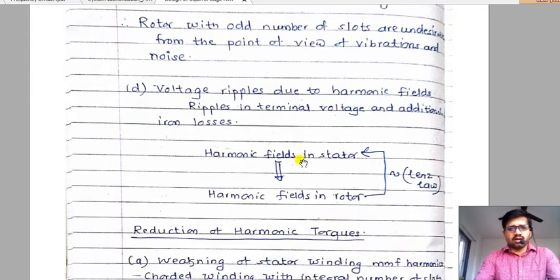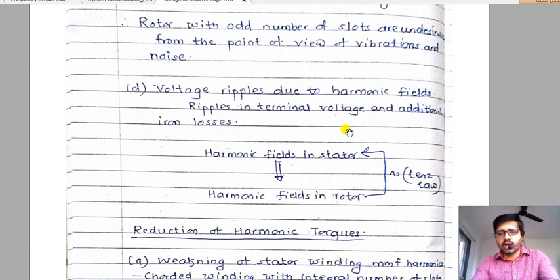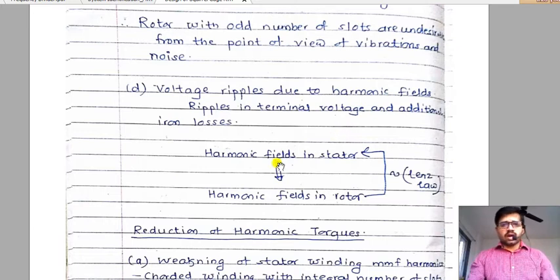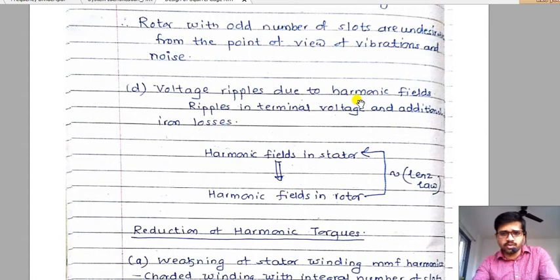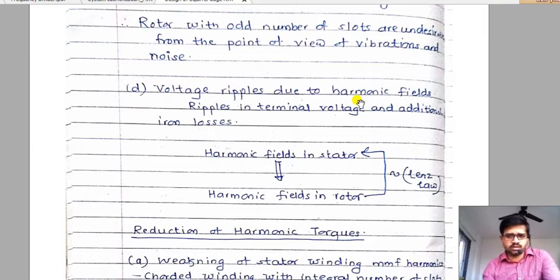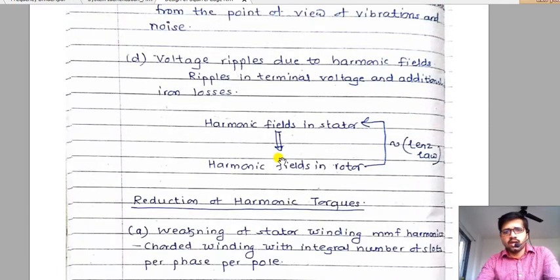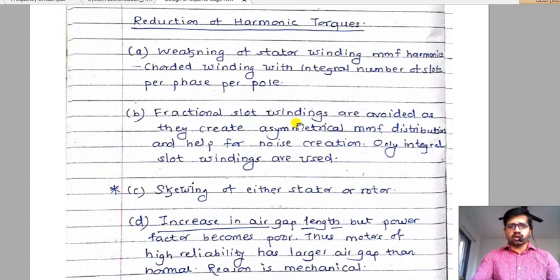Another effect is voltage ripples caused by harmonic fields. Whatever happens in the rotor is an effect of what happens in the stator. Harmonic fields in the stator induce harmonic fields in the rotor, and by Lenz's law those rotor harmonic fields induce back harmonic fields in the stator, causing ripples in the terminal voltage and additional iron losses.